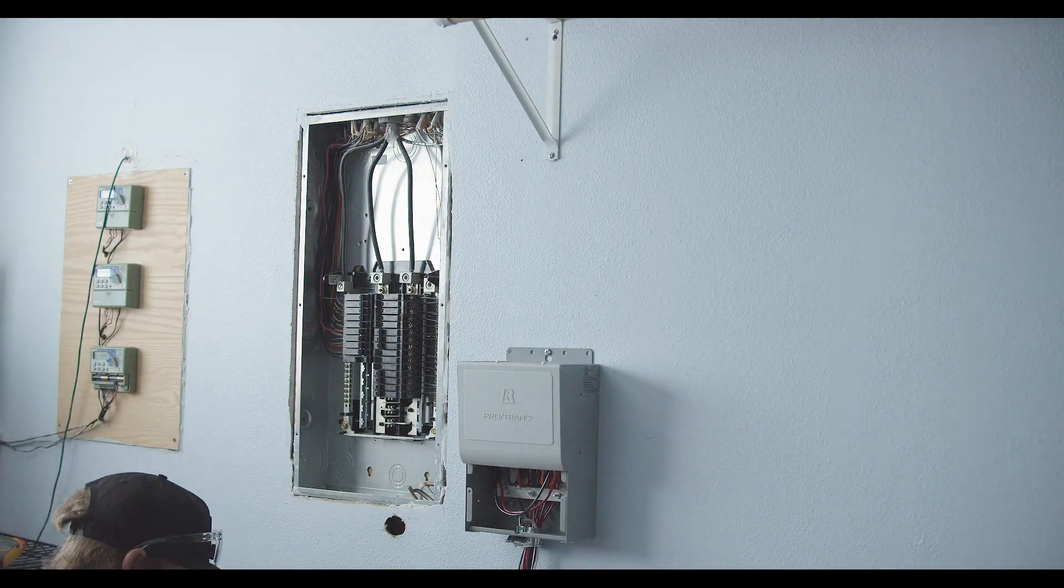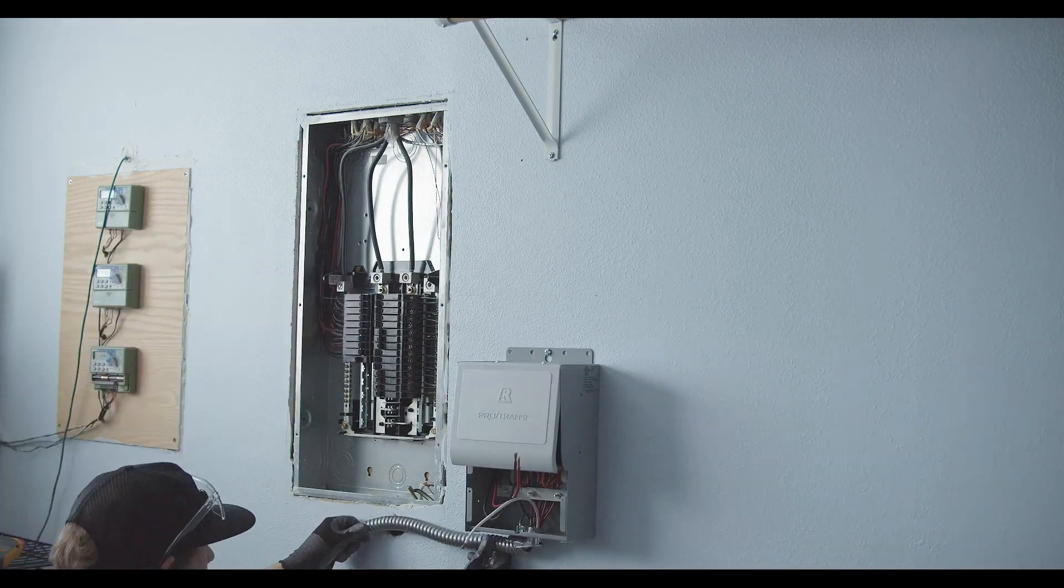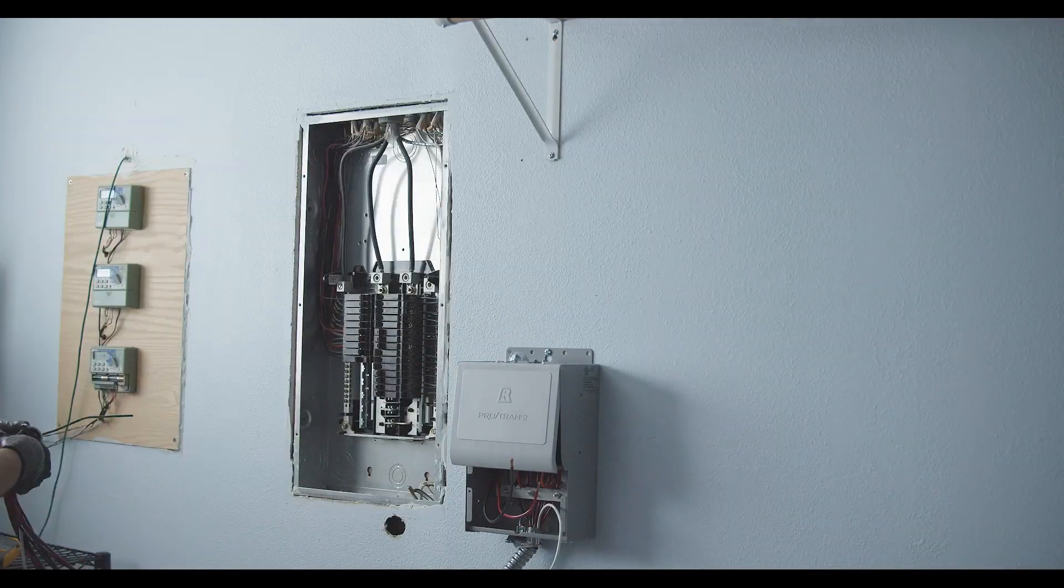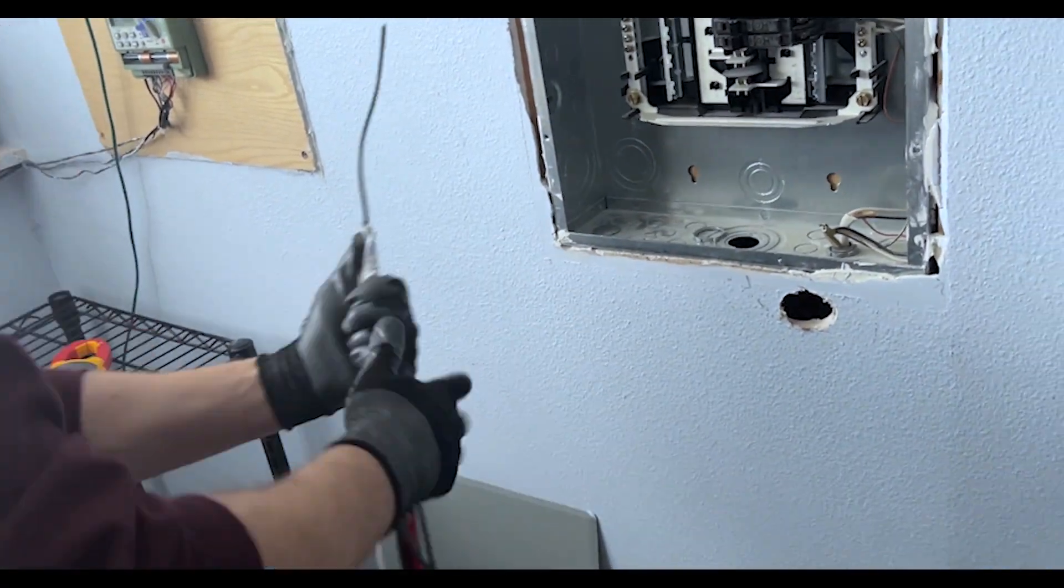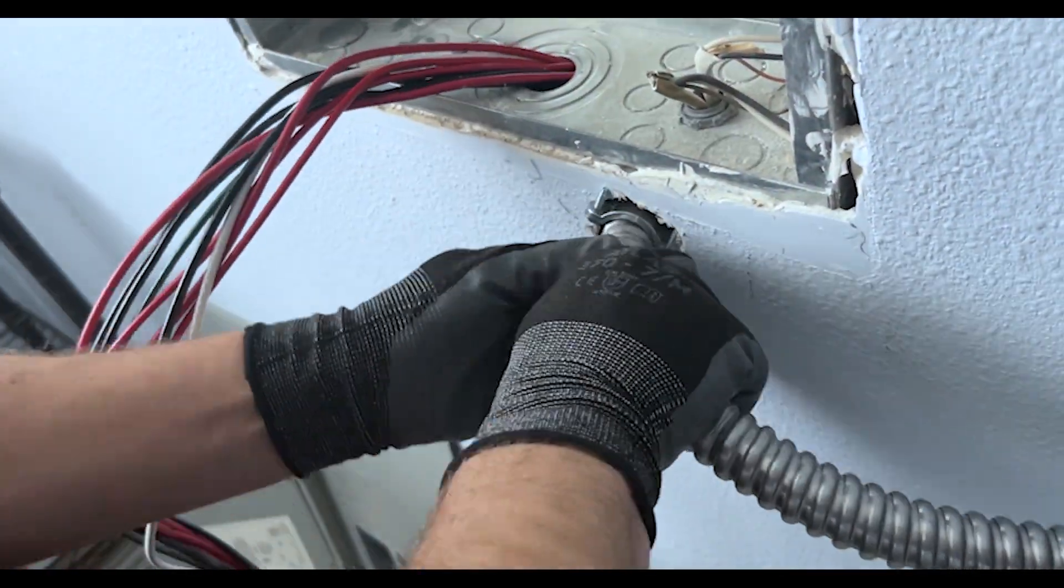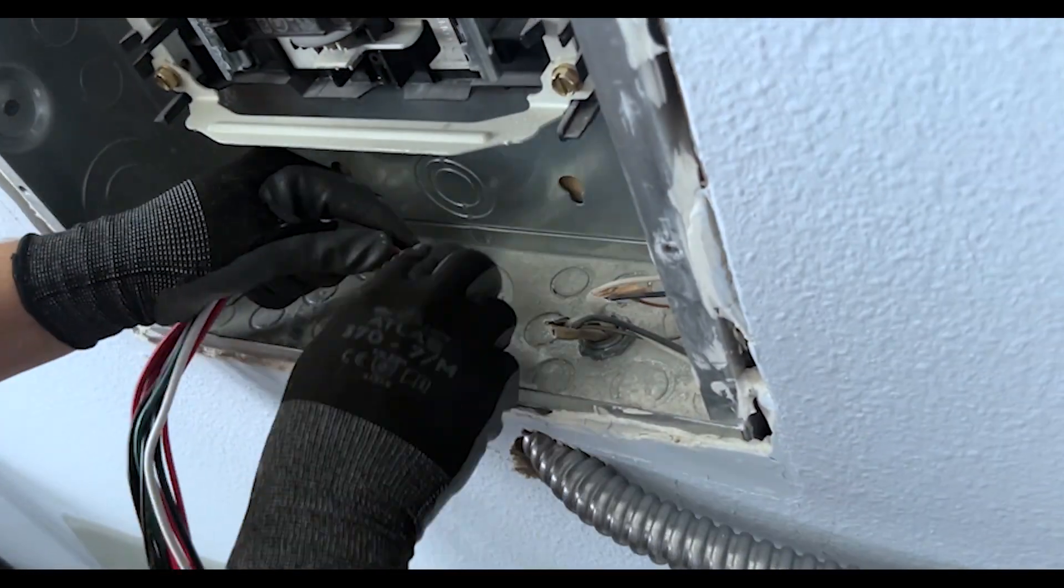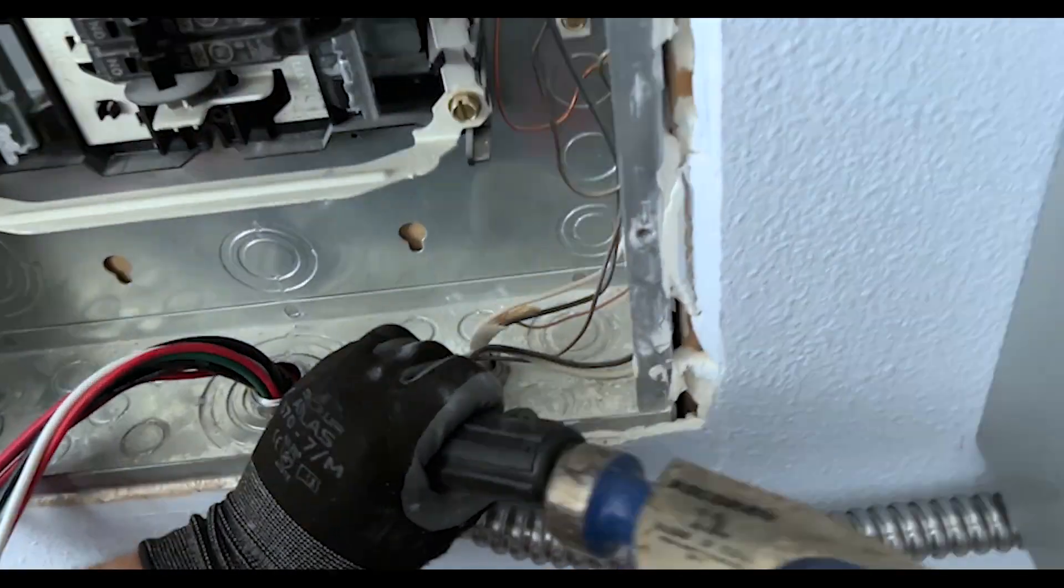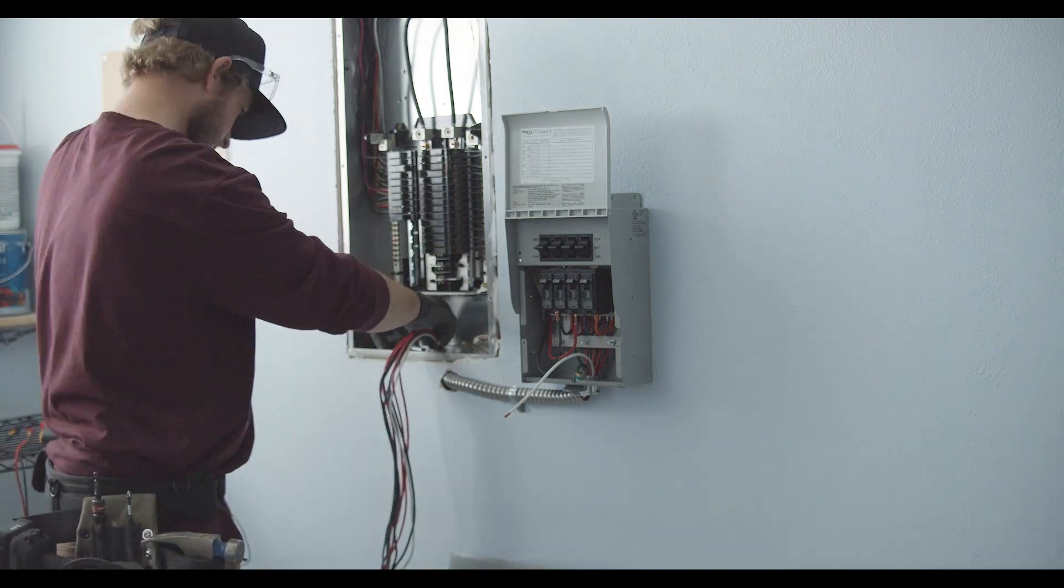Once I've removed the knockout on the bottom of the sub panel I'm going to feed the flexible metallic conduit around those wires that come on the transfer switch and then feed that through the hole and then up through the knockout in the bottom of the sub panel. There is an angled bracket that comes with the flexible metallic conduit that I'm feeding through the wall and then it goes through that three-quarter inch knockout and then you have a lock washer that goes on that that you can tighten down.